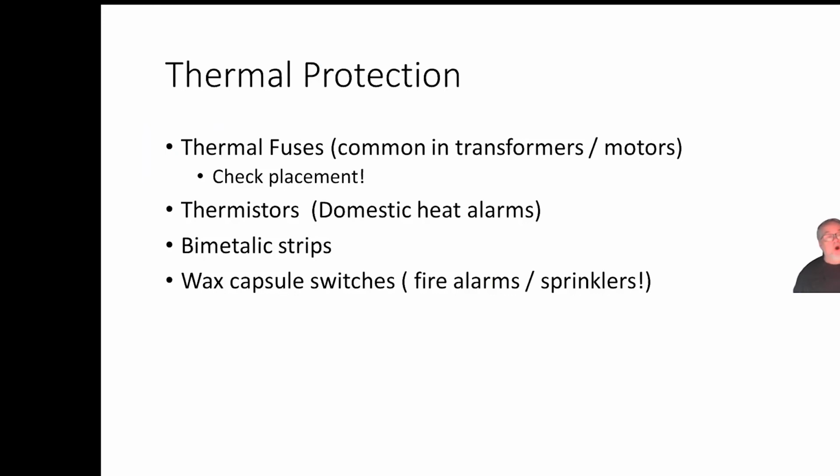Thermal fuses are common in transformers and motors. Very often, if you look at a transformer, there's something stuffed into the windings. And you pull it out and it looks like a wee fuse. And it is a fuse, but it's a thermal fuse. It's not designed to blow at a certain current or at a certain voltage. It's designed to blow when the temperature goes above a certain level.